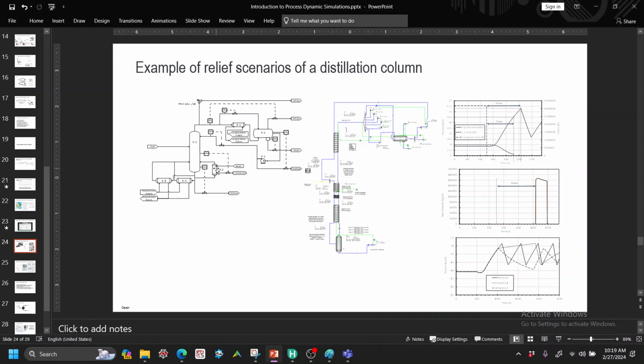So in this case you have three reboilers. These two are big reboilers coming from an FCC tower somewhere, and this is your steam reboiler. So this is just a heat integration effort, and there is no control whatsoever here. If that FCC tower fails, we don't have enough energy supplied to this column. Because this is downstream, if that thing fails, this will stop anyway. But they have this steam reboiler which they can use to polish the performance of the column slightly.